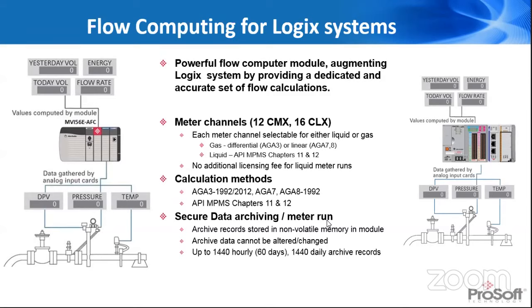So as we've talked about the API requirements, we've got two different platforms, ControlLogix and CompactLogix. Our ControlLogix allows for up to 16 measurement runs, and those can be any combination of gas or liquid measurement runs. Certain other devices out there have a limitation of 6 gas and 6 liquid, or 12 gas total, but you can only do 6 liquid. This can do all 16 liquid, all 16 gas. It's up to the user to select that.